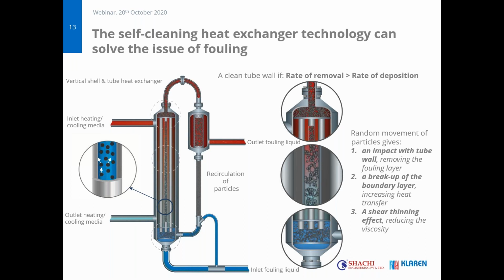In our system, we use tube velocities which are lower than normal. If you would take a nowadays well-designed shell and tube heat exchanger, it would run with tube velocities over 2 meters per second. And we even now sometimes see close to 3 meters per second or over. But we run with lower velocities.